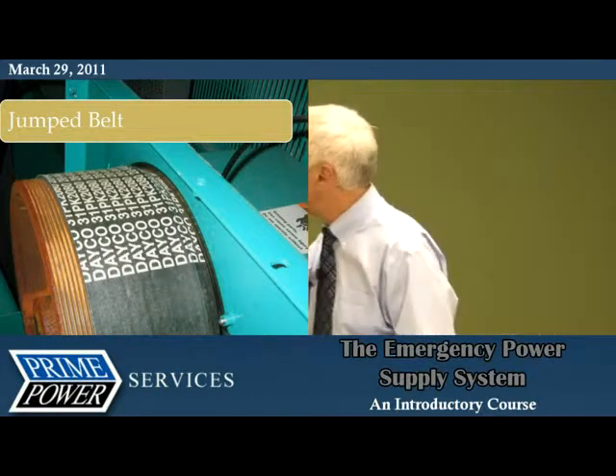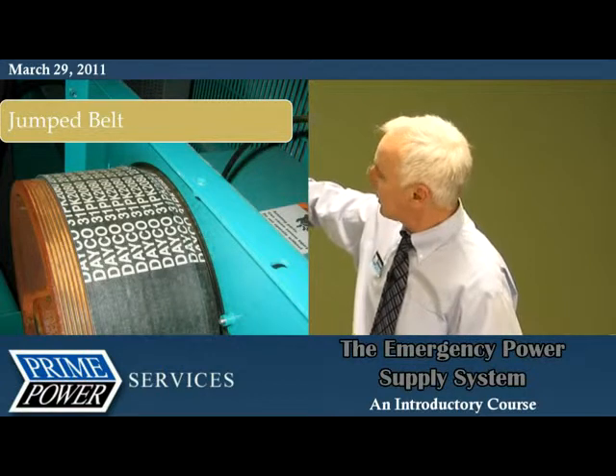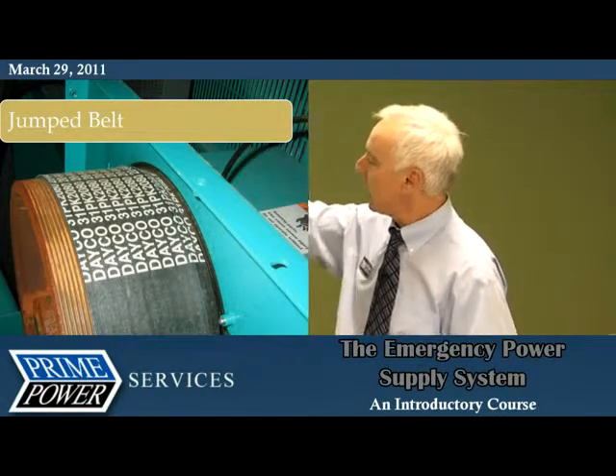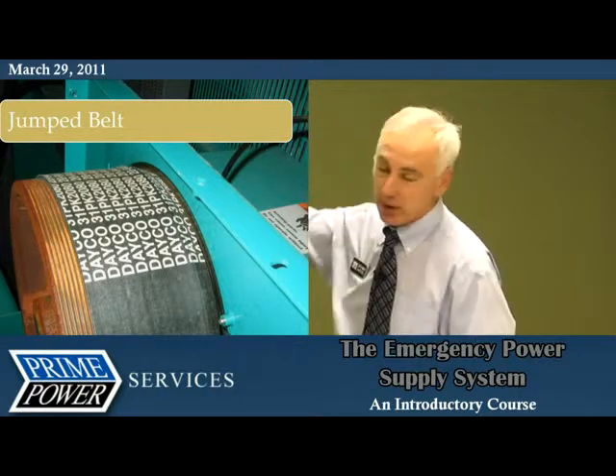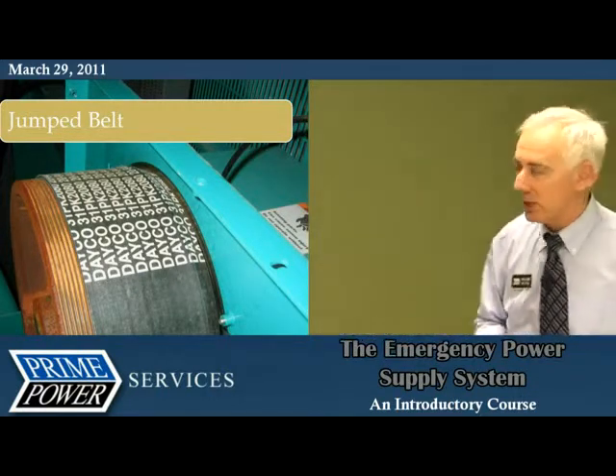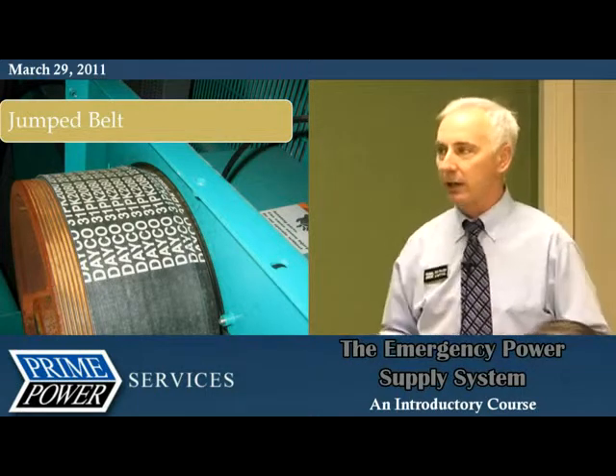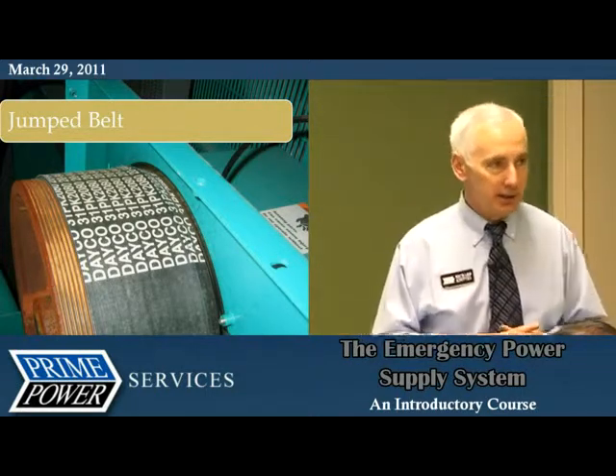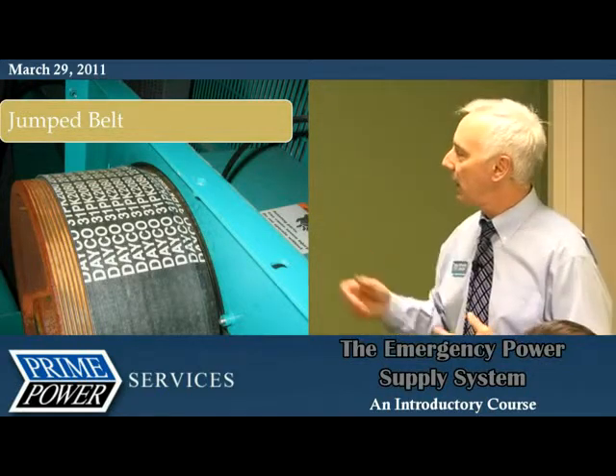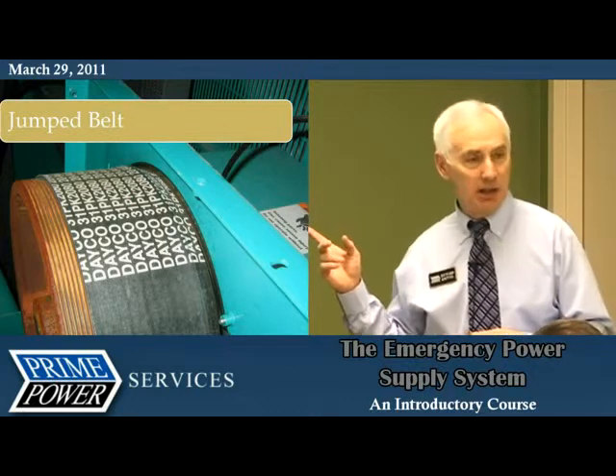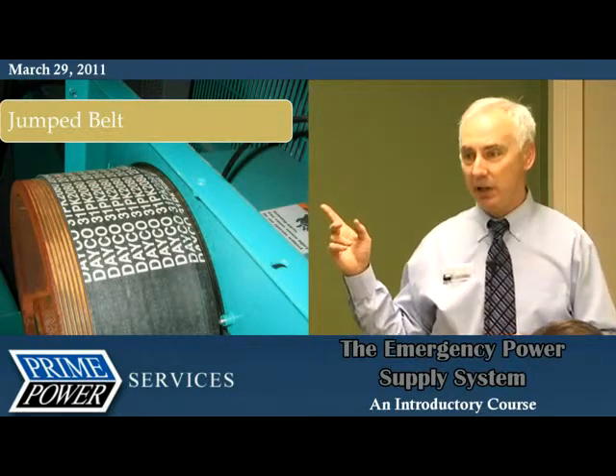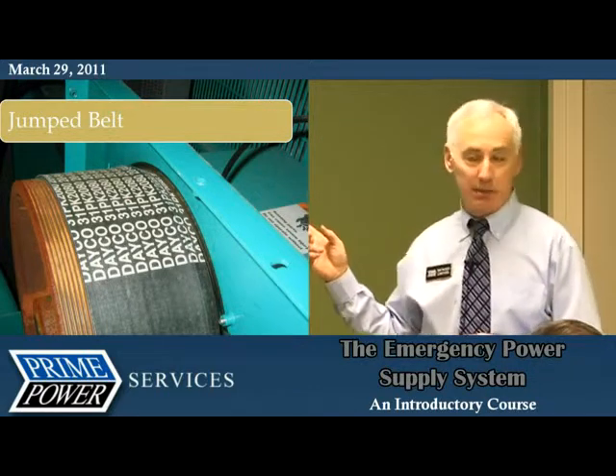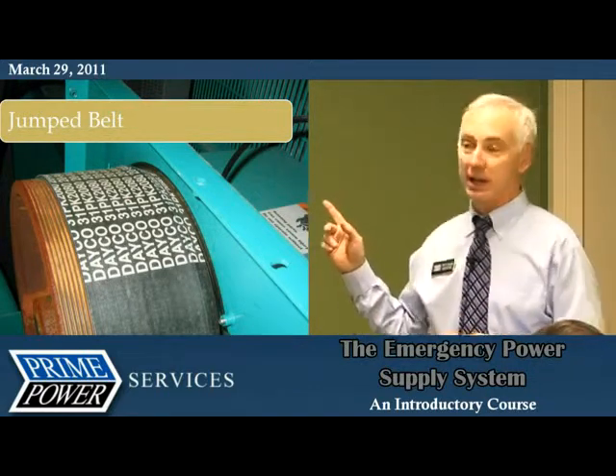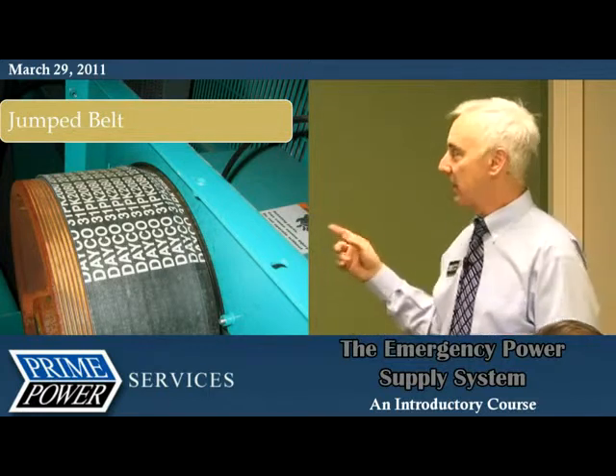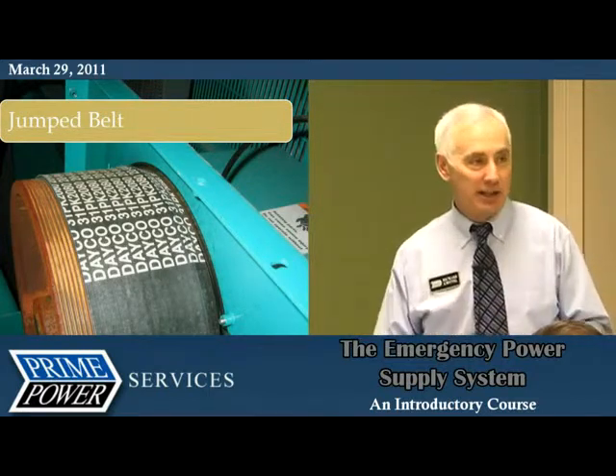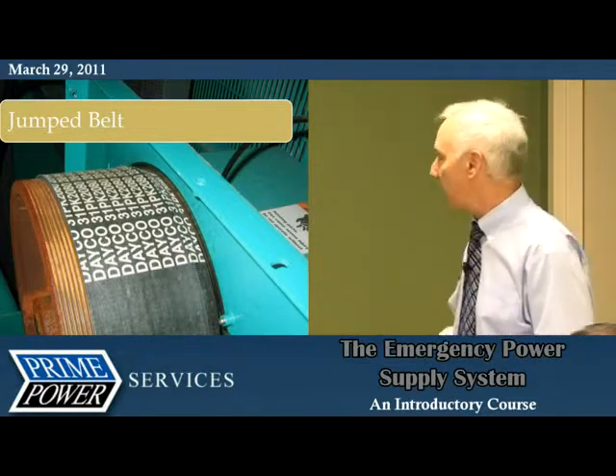Thank goodness for the metal on the back side of that, because that's the only thing that kept this misaligned pulley from walking the belt farther off. But here again, this was an existing site, we're just walking around looking at it, not really nitpicking. But when a belt starts shredding while spinning at 1800 RPM, that belt is like a tire coming off, and anything in its way gets taken with it. So it's not just that the fan's not turning, it's that the fan has been peeled off and shoved through the radiator.